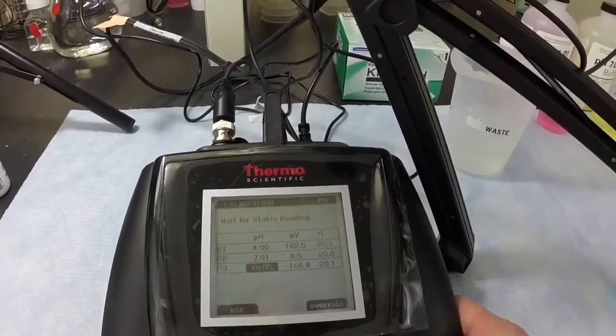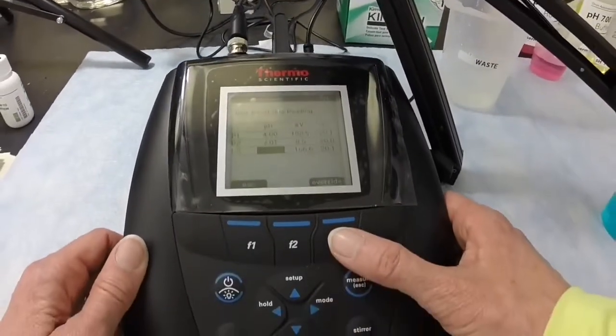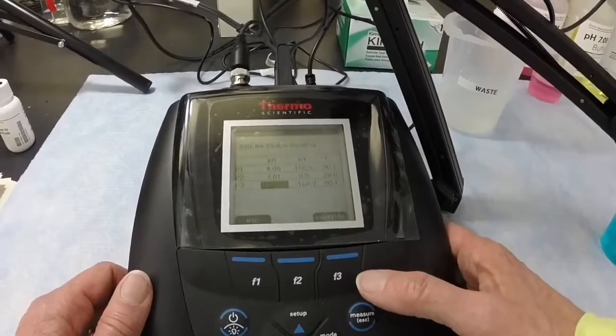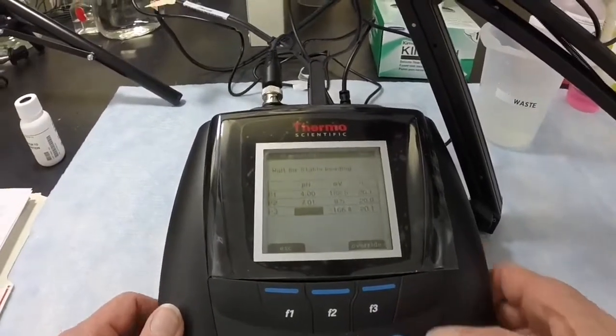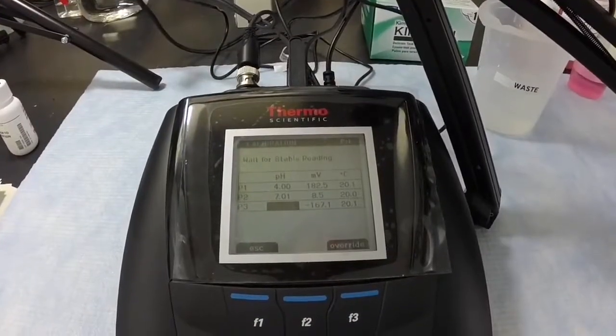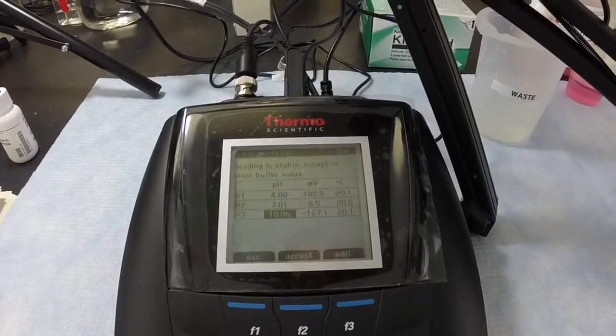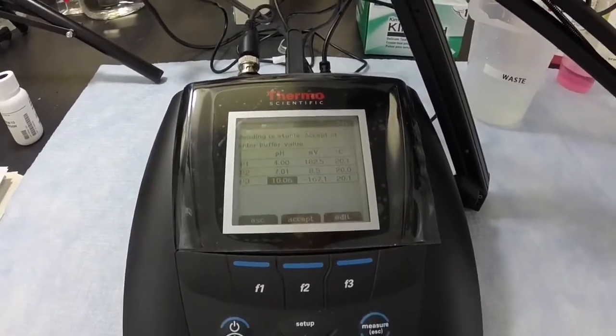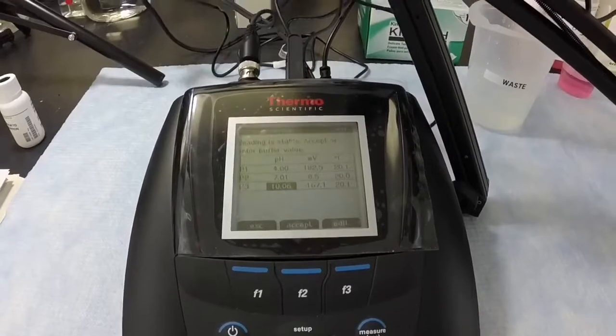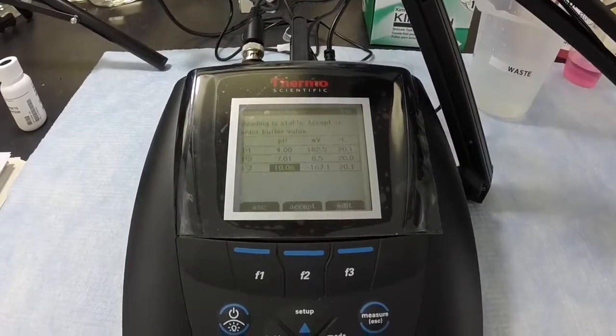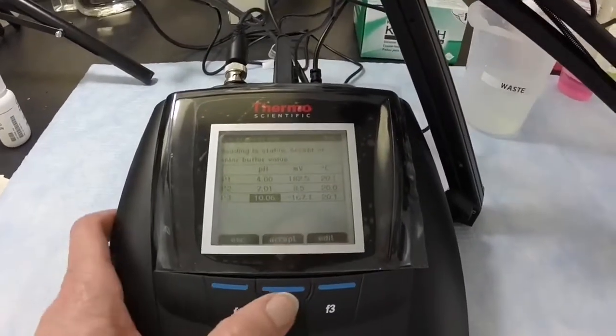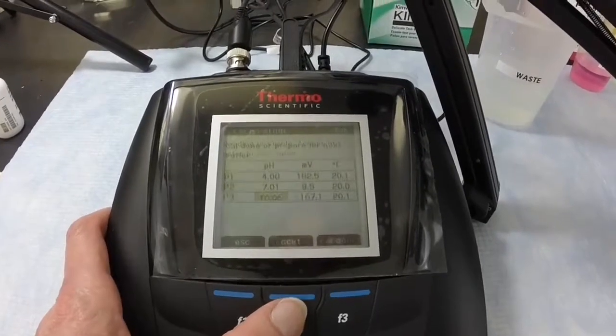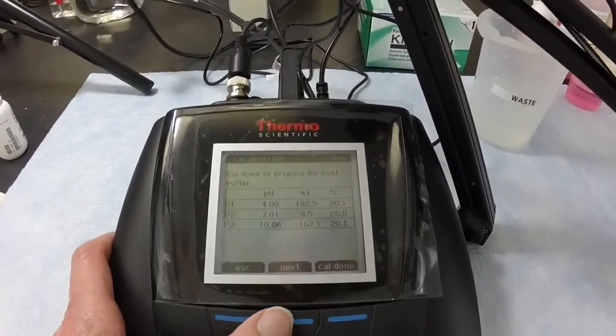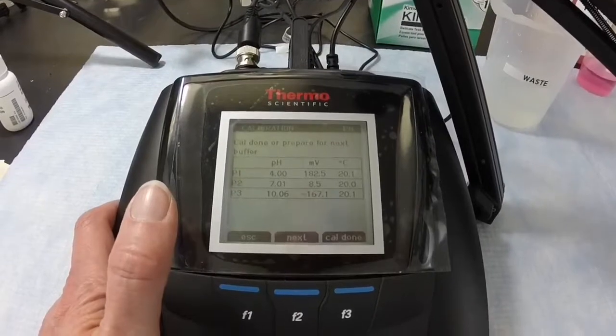We can see all 3 calibration points on the meter display, including the pH, the millivolt value, and the temperature. When the reading is stable, the reading will freeze, and the correct pH value for that temperature will display. We will choose Accept. Since we're doing a 3-point calibration, we are done. So we choose Cal Done.